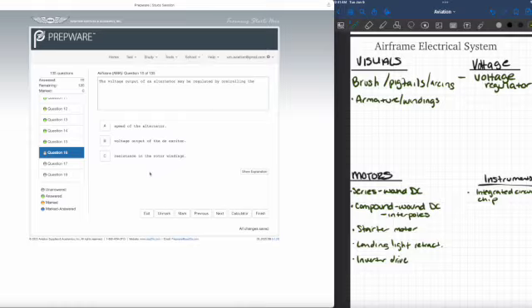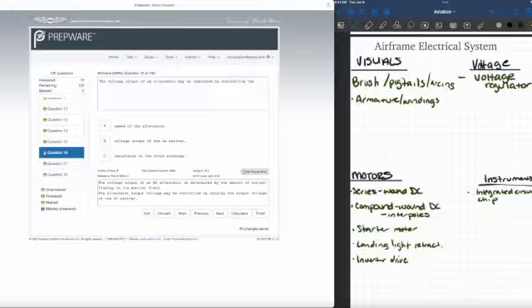The voltage output of an alternator may be regulated by controlling the A. speed of the alternator, B. voltage output of the DC exciter, or C. resistance of the rotor windings. The answer is the voltage output of the exciter. The voltage output of an AC alternator is determined by the amount of current flowing in its exciter field. The alternator output voltage may be controlled by varying the output voltage of the DC exciter. Key term: AC alternator.